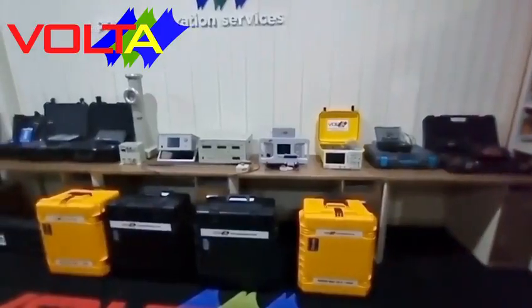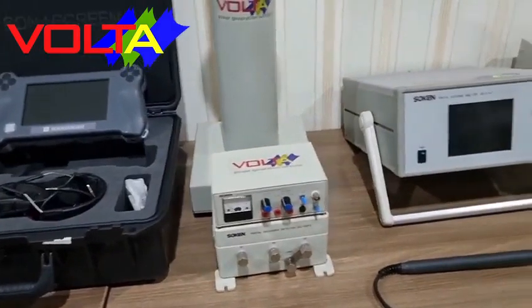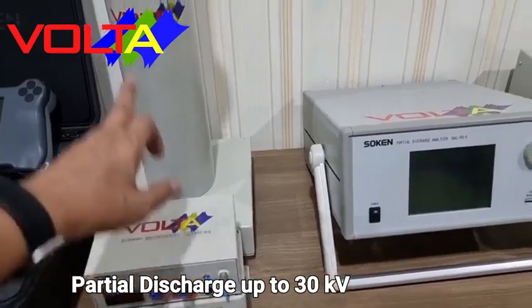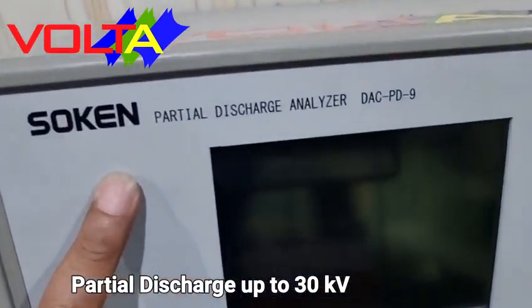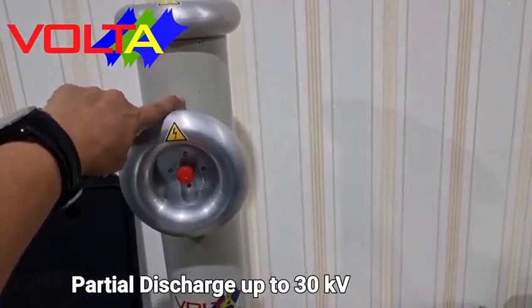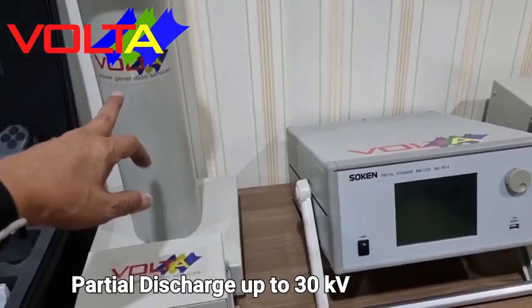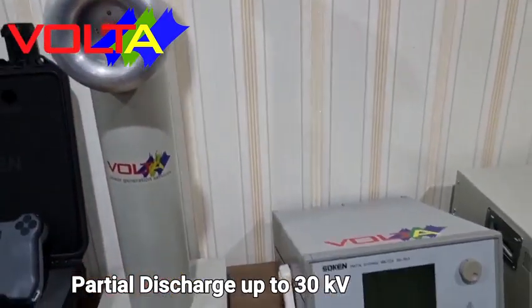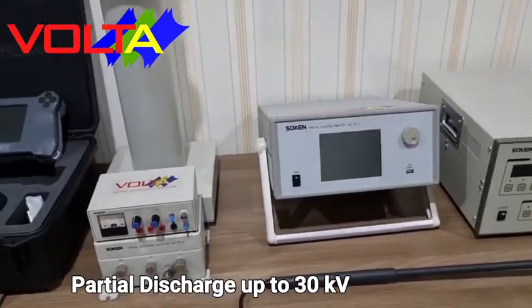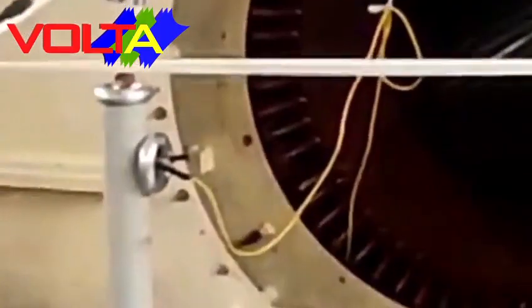Here are our own test instrument facilities. For partial discharge testing, we provide three partial discharge test instruments. The first is the Soken type DAC-PD-9. Our instrument is provided with a blocking coil and capacitor coupler of 1000 picofarad, 30 kilovolts. It is able to analyze partial discharge precisely. Depending on the power supply capacity, the Soken DAC-PD-9 is able to test large size generators with voltage range up to 30 kilovolts.